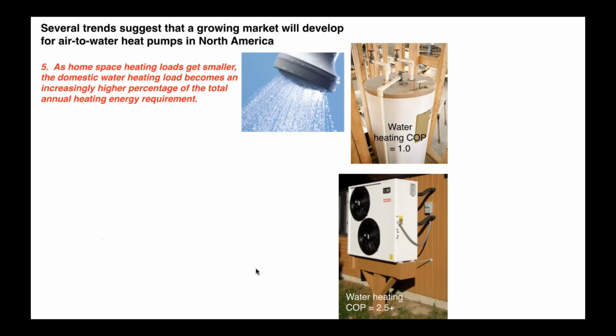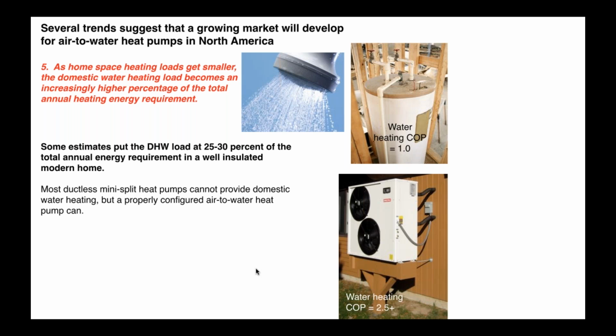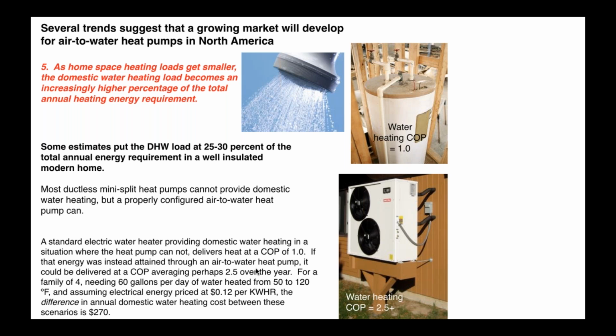So another thing, domestic water heating. You can't really do that. Well, I shouldn't say you can't do that with certain geo systems with these desuperheaters, but you really can't do that with a ductless mini split. And what's happening as house heating loads are getting smaller, the domestic water load can be anywhere from 25 to 30%. And real quickly, I've done the math on this. Family of 4, 60 gallons per day of domestic water heated from 50 to 120 degrees Fahrenheit. If you do it with an electric water heater versus doing it with a heat pump, and assuming a seasonal average heating coefficient of performance of 2.5, you're actually saving about $270 a year just in domestic water heating compared to doing it with electric resistance heat. So it's not always just about space heating or cooling. That domestic water load is significant.